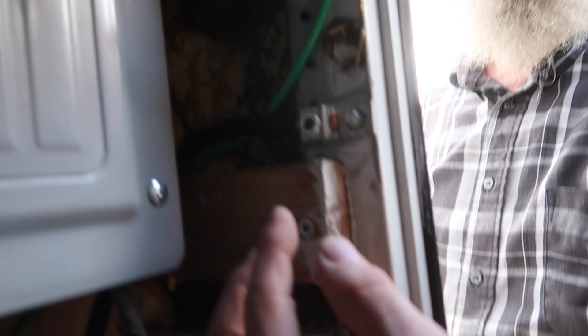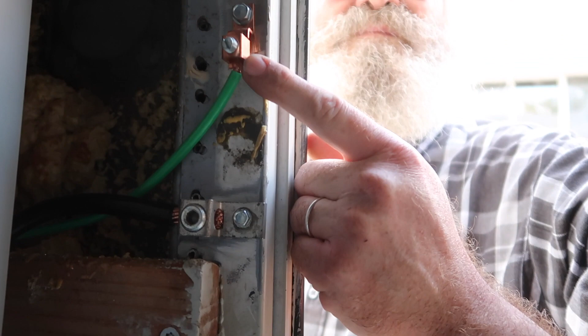Around the corner, inside of here, we have a couple of really important grounds. This one is your solar photovoltaic lightning discharge protector. It's not going to protect you from a lightning strike — what it does is constantly de-energize the electrostatic charge that builds up when you're underneath lightning.